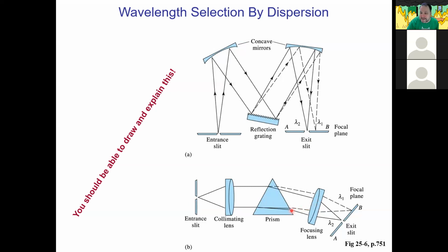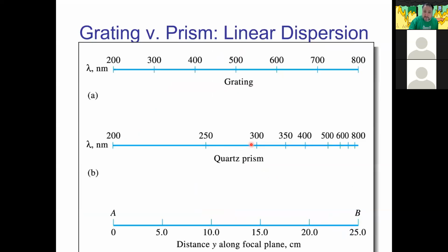You end up with rainbows happening where either one wavelength gets refocused on the focal plane over here to hit the wall, and the other one is able to make it through the slit. Again, you're going to rotate that prism around. If we had an old Spec 20, I would show you how that works, where you've got a knob, and that knob moves a little arm, and that little arm basically rotates one of these things. So this is how your wavelength selection works by dispersion.